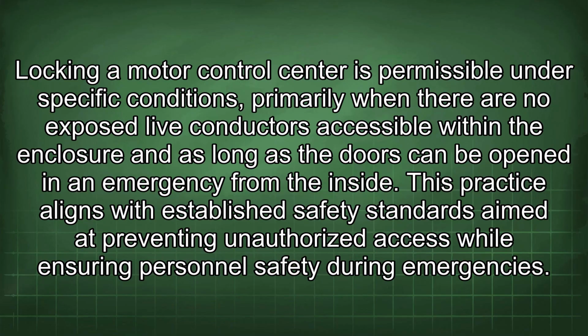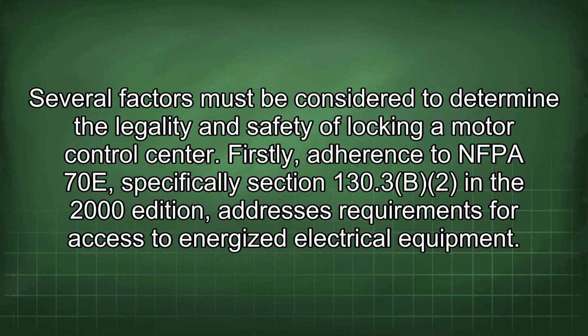Locking a motor control center is permissible under specific conditions, primarily when there are no exposed live conductors accessible within the enclosure and as long as the doors can be opened in an emergency from the inside. This practice aligns with established safety standards aimed at preventing unauthorized access while ensuring personnel safety during emergencies. Several factors must be considered to determine the legality and safety of locking a motor control center.